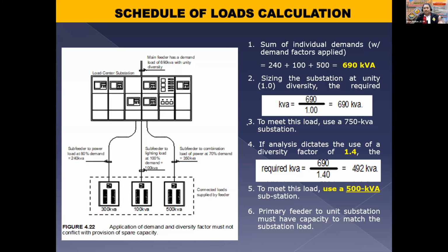So, si diversity factor, hindi natin ito ma-apply sa mga sub-feeders, ha? Doon lang sa mains natin ma-apply si diversity factor. Yung sa mga feeders natin, si demand factor yan. Okay? So, yun yung difference ng dalawa. Okay? So, I think this is it for the first part.